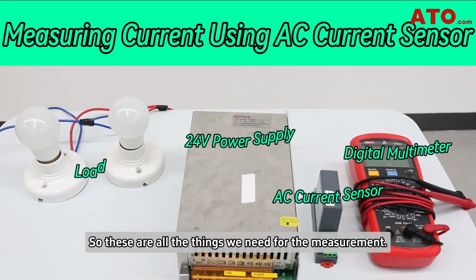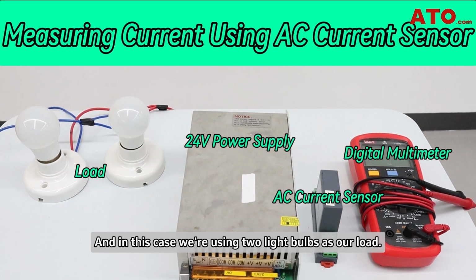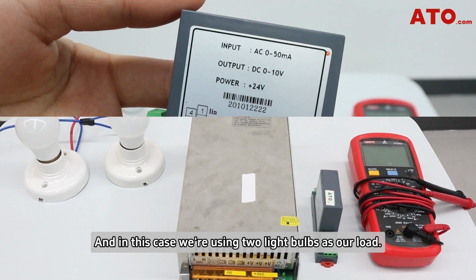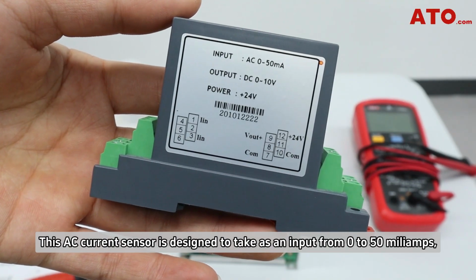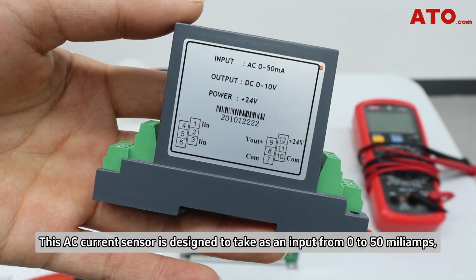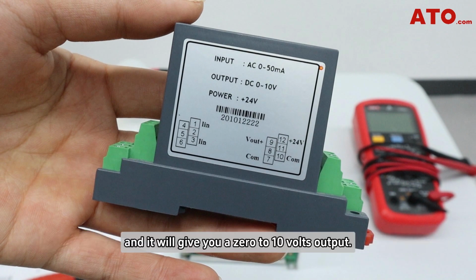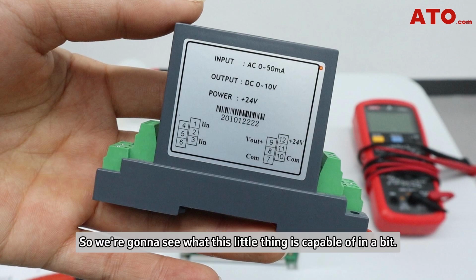These are all the things we need for the measurement, and in this case we're using 2 light bulbs as our load. This AC current sensor is designed to take an input from 0 to 50 milliamps, and it'll give you a 0 to 10 volts output, and it requires 24 volts to power it. We're gonna see what this little thing is capable of in a bit.